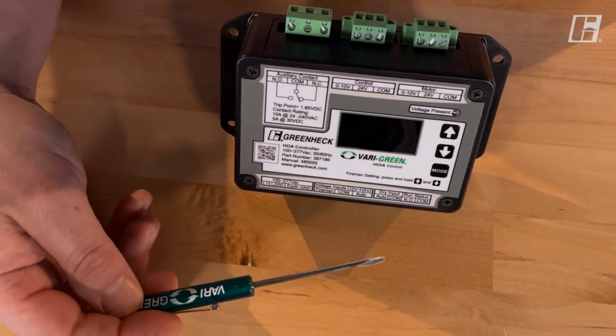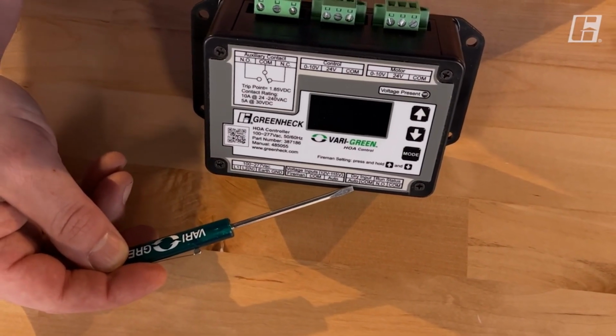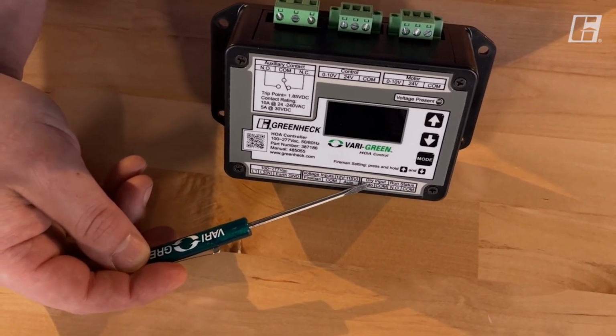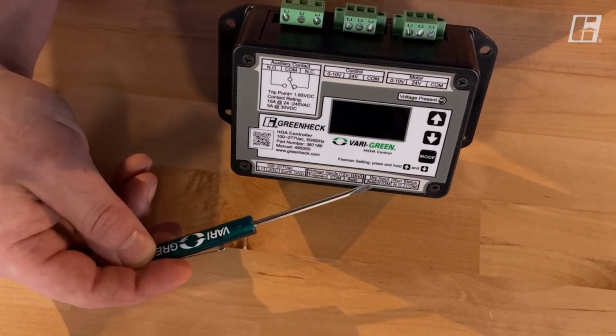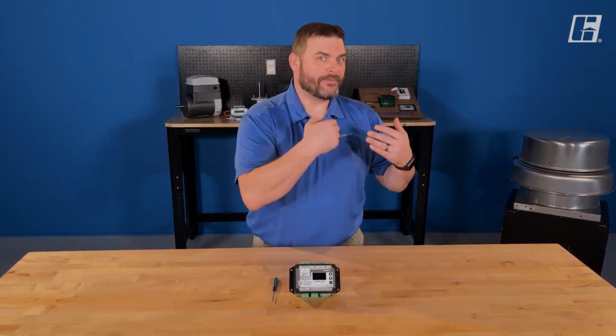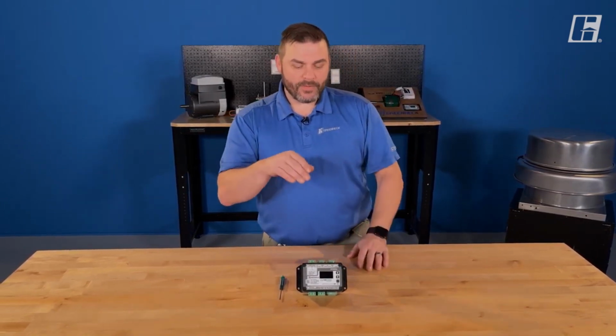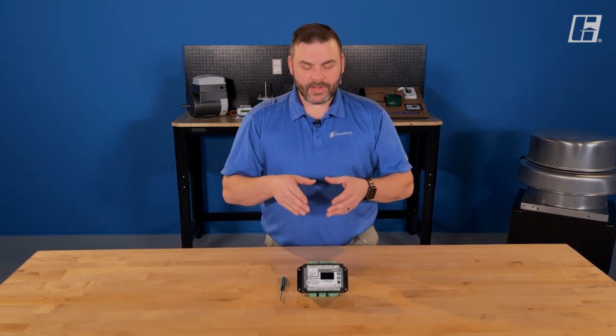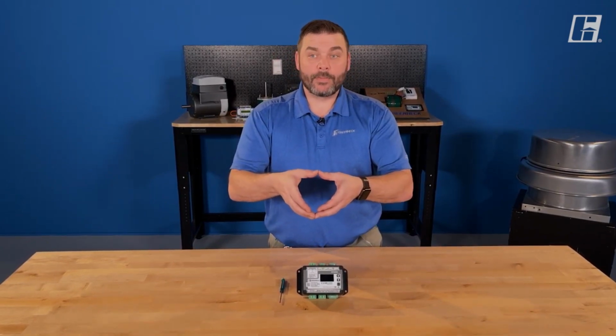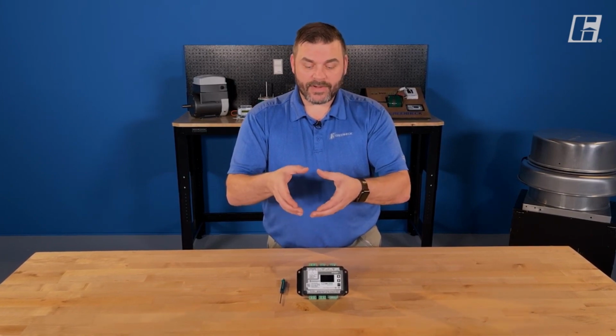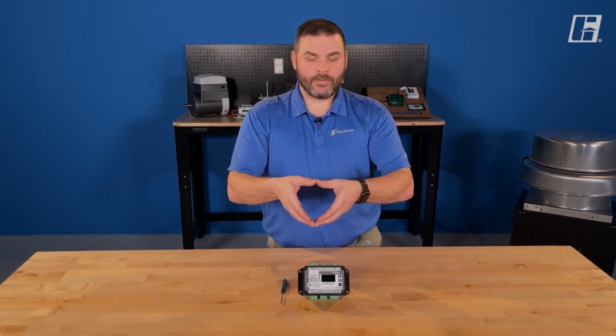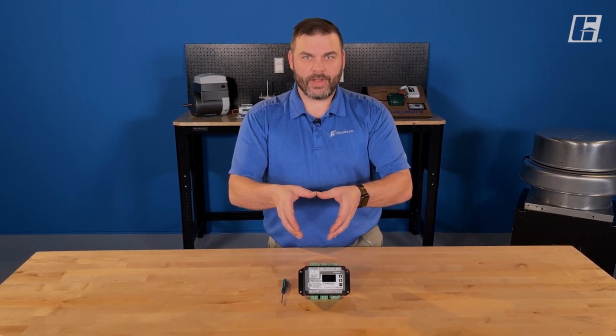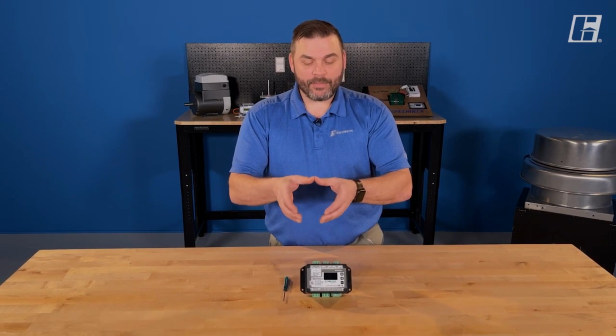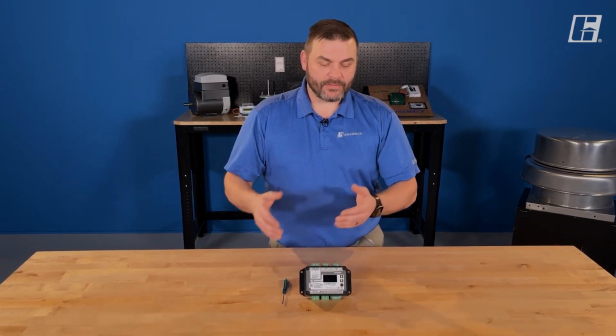Now our next sets of terminals, let's start here. We have our dry auto or dry input terminals. There's an auto and a common. There are 2 common ways of communicating in our industry, and that's using a dry contact or a wet or a voltage contact, right? So for the dry ones we just talked about here, I'm looking for a complete circuit, or I'm looking for continuity. When I have a complete circuit, you're telling me to run. When I break that circuit, or open a switch, or open a relay, anything that breaks that circuit, you're telling me to stop. So that's the dry side.